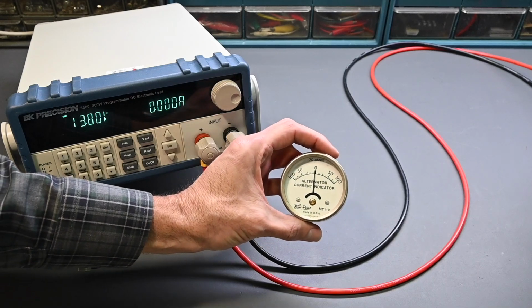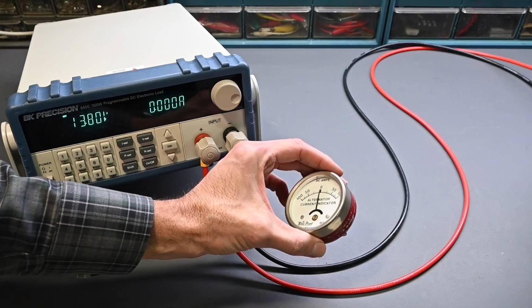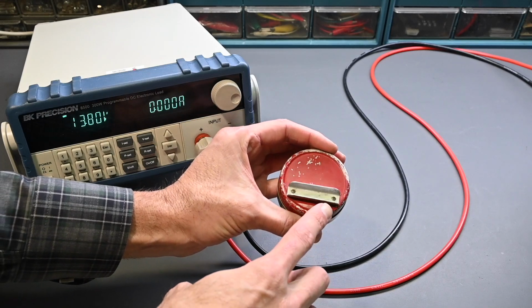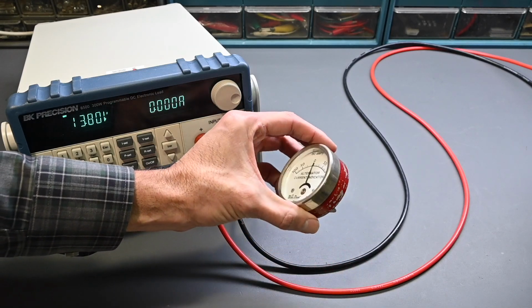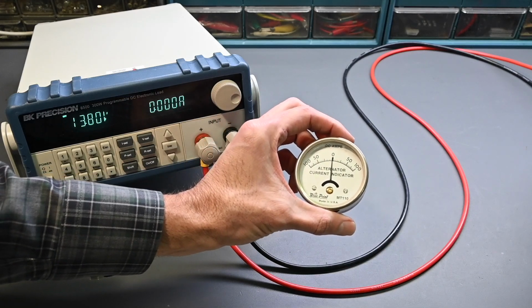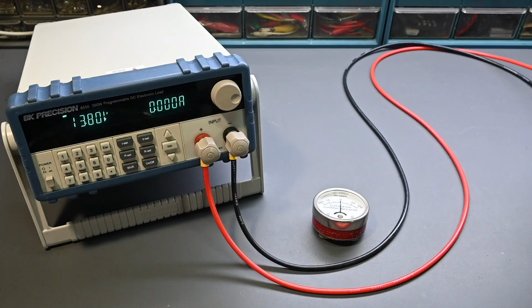And these induction ammeters are extremely easy to use because to use them, you just place the wire that you want to measure in this channel on the back. So a big advantage of the induction ammeter is that it doesn't require breaking into the circuit. Now the accuracy on these types of meters is typically lower than other methods, and insulation thickness can affect the accuracy, and I'll show you that in just a moment. And these are best for higher current levels, really limited only by the range of the meter scale. And of course, you're not going to be measuring down into the microamp range with a meter like this. And these are a passive design, so they don't require any kind of power like a battery or something like that. It's basically powered off the magnetic field around the wire.